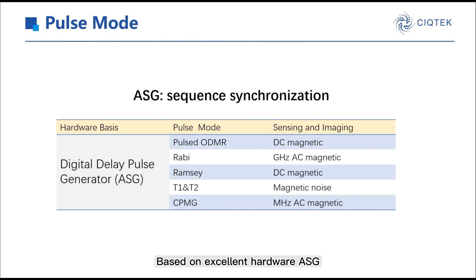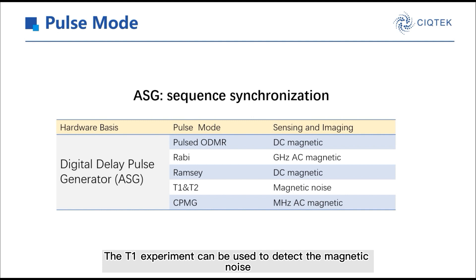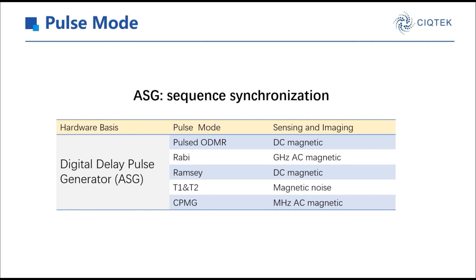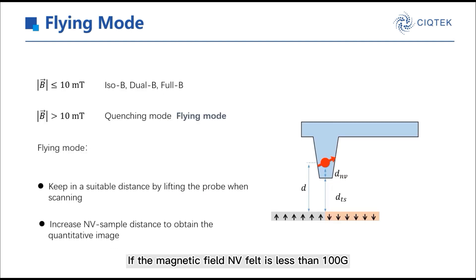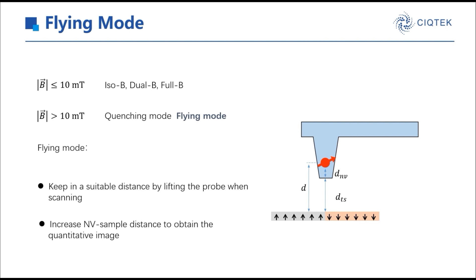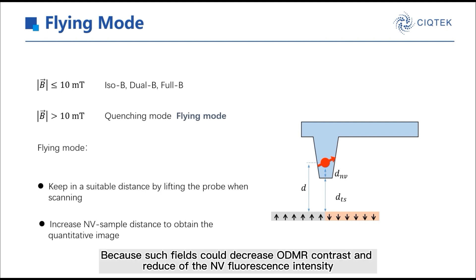Based on excellent hardware ASG, pulse experiments can be realized in QDEFM. Pulse mode can enrich the function of QDEFM greatly. For example, the T1 experiment can be used to detect magnetic noise. Pulsed ODMR or Ramsey has better sensitivity in sensing DC magnetic fields. If the magnetic field the NV senses is less than 100 Gauss, the suitable methods we apply are Iso-B, Dual-B, or Full-B mode. These methods can achieve quantitative or semi-quantitative analysis. However, if more than 100 Gauss, we can only use the quenching mode generally, which is non-quantitative, because such fields could decrease ODMR contrast and reduce the NV fluorescence intensity.